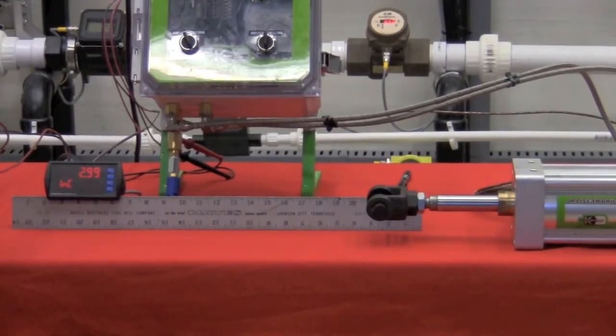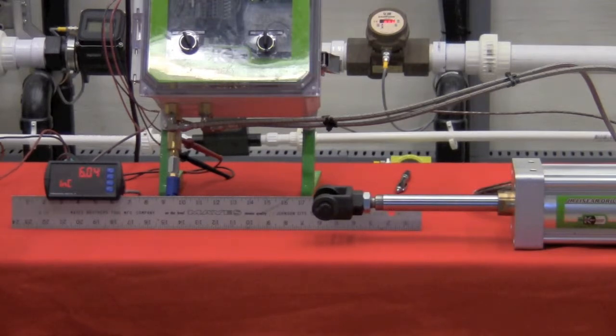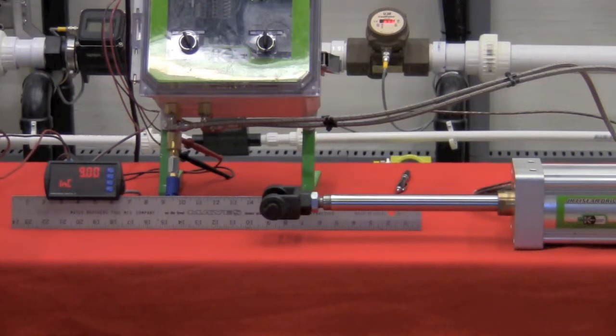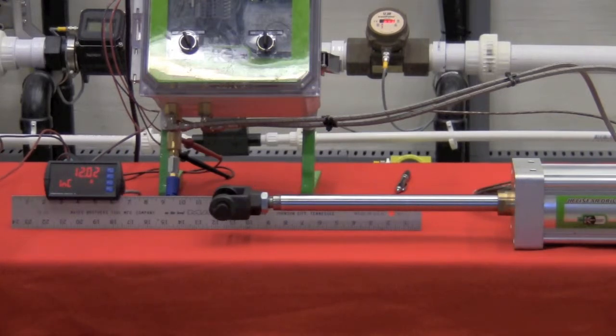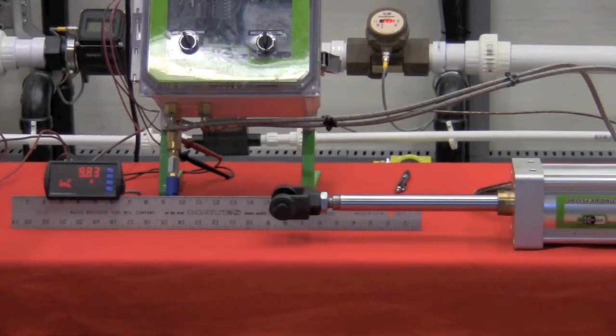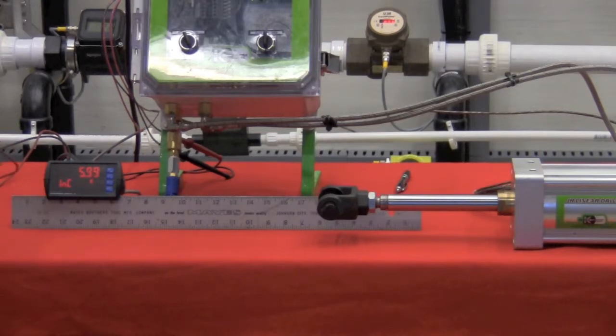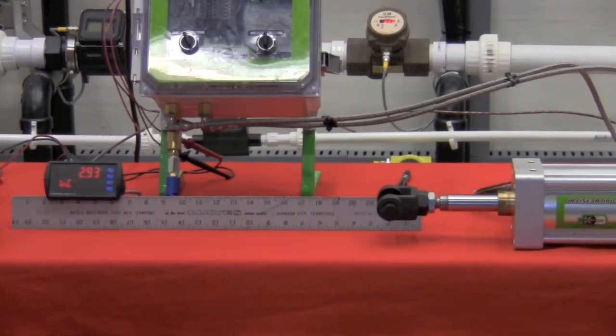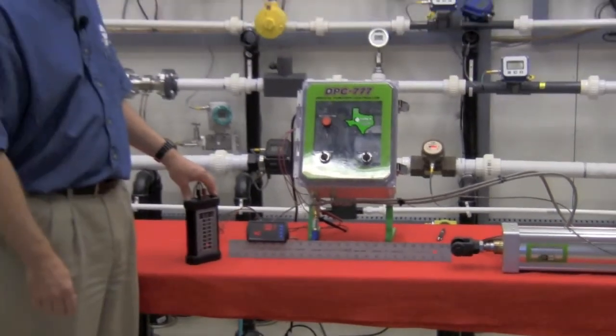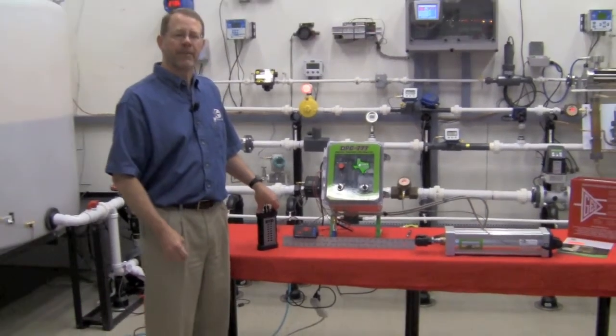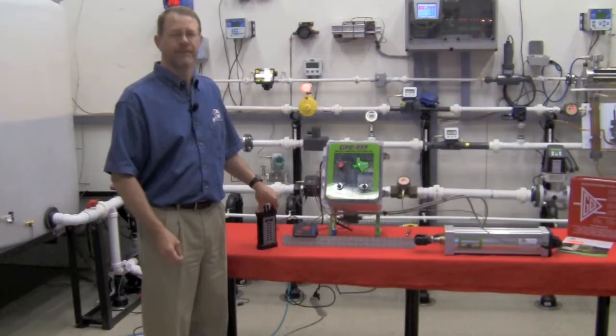8 milliamp we're at 3 inches. 12 milliamp we're at 6 inches. 16 milliamp 9 inches, and 20 milliamp 12.02 inches. Let's return to 12 milliamp, which should be 6 inches. And we are. And then we'll go back to 4 milliamp. I hope you noticed that each stop was within 1/20th of an inch.